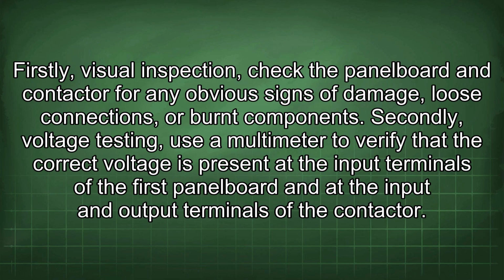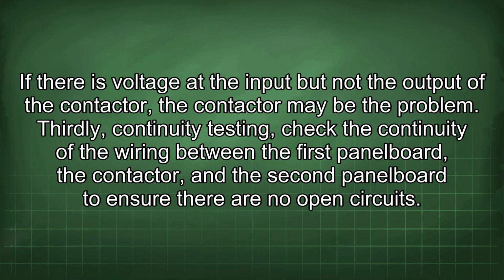Secondly, voltage testing. Use a multimeter to verify that the correct voltage is present at the input terminals of the first panel board and at the input and output terminals of the contactor. If there is voltage at the input but not the output, the contactor may be the problem.